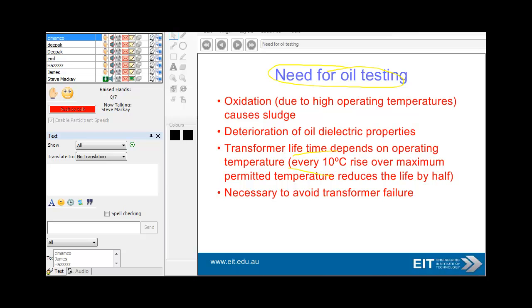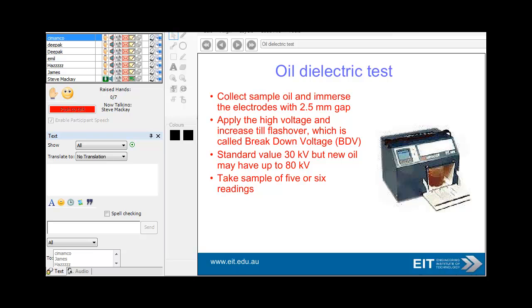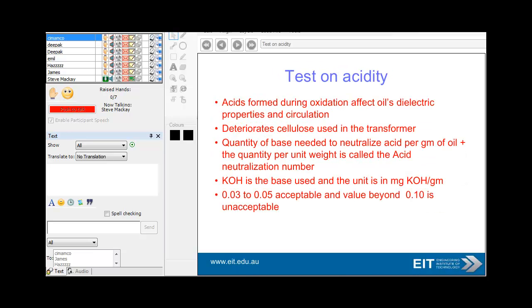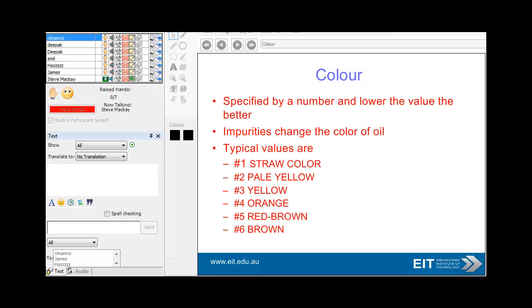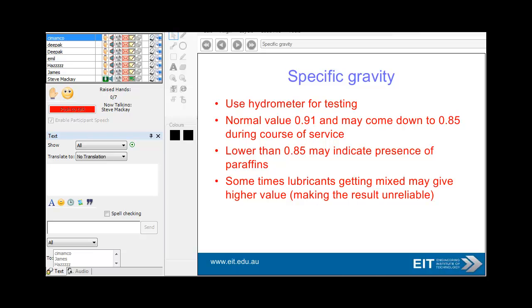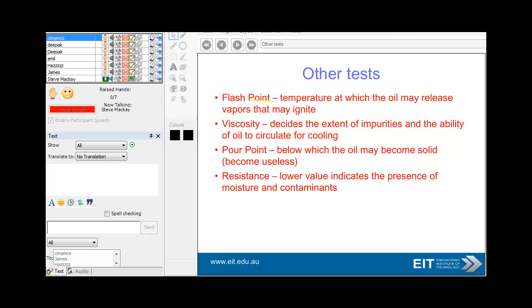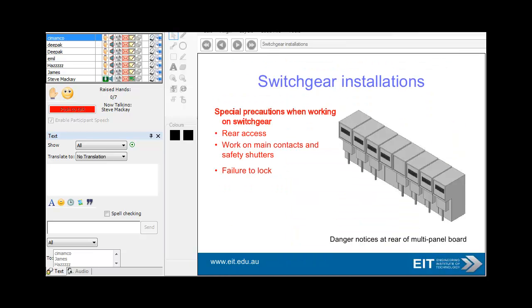Transformer lifetime depends on operating temperature — obviously, the hotter it is, the shorter the life. It is critical to avoid transformer failure, because an explosion or failure of a transformer can bring a whole suburb or plant out. Oil dielectric tests include checking for acidity, interfacial tension, and color — the lower the value, the better. Impurities change the color of the oil, so brown is not very good, while straw or yellowish color is very good. Also check specific gravity, flash point, viscosity, pour point, and resistance, trying to eliminate any contaminants or degradation.